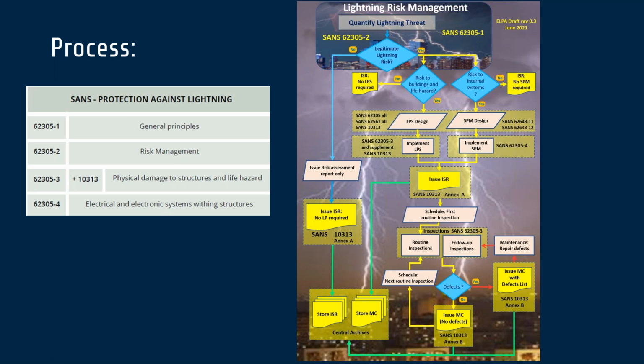The IEC standards have numerous modules that apply directly to our surge protection, but we have not adopted them because of other legitimate reasons. SANS 10142-1 has been legislated through the electrical installation regulations, and as a result, the way that we populate it has to be considered in methods whereby the chief health and safety inspector, when he walks in and deems that there has been a fault, can hold somebody accountable, knowing that that person had the opportunity to obtain the necessary skills and simply failed to do so.